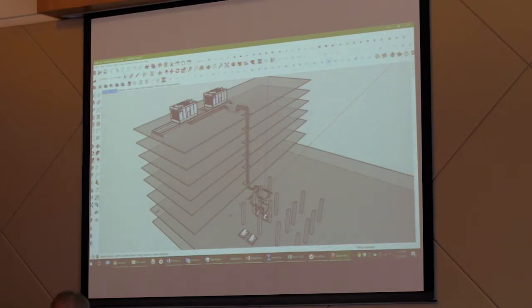So if I did that open loop test with everything running, that apparent dead time would be a minute and a half plus if everything was running. If only the little chiller is running, it'd be 15 minutes before I'd see a reaction, okay, at least. That makes it very challenging to tune the control loop, right? So what I do with the model is I talk to them about lags, I get them to see the problem, and then I say, well, how could you solve that problem? In other words, I guess actually what I'll ask them is, how would you control these cooling towers? And so that gets into a discussion, are the bypass valves and the cooling towers trying to do the same thing or the opposite thing?